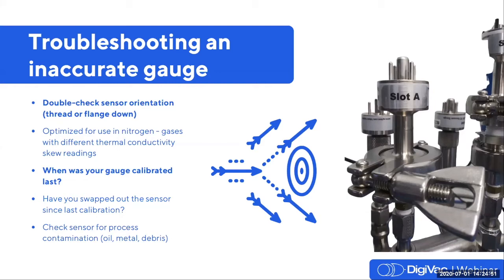Our instruments, and thermocouple type instruments in particular, are optimized for use in nitrogen. So gases with different thermal conductivity will skew readings. This is an issue we tackle in tech support from time to time. A customer will be attempting to use their thermocouple sensor in particularly noble gases such as argon or neon, and they'll wonder why their gauge is reading so off.